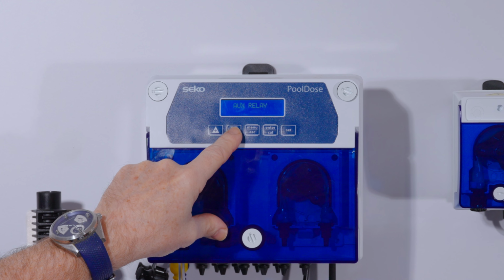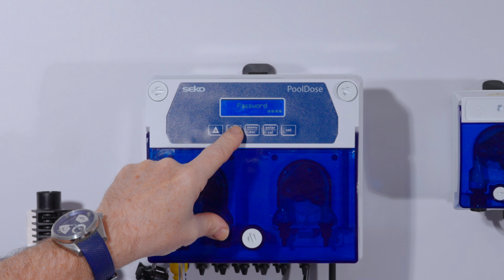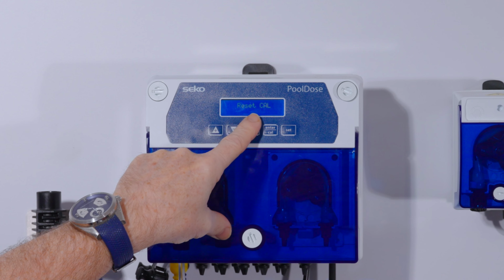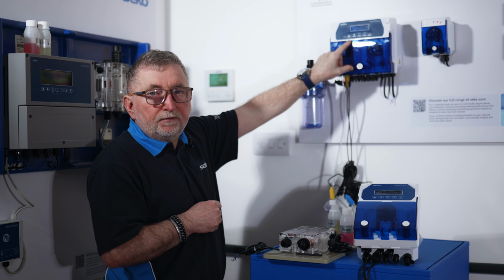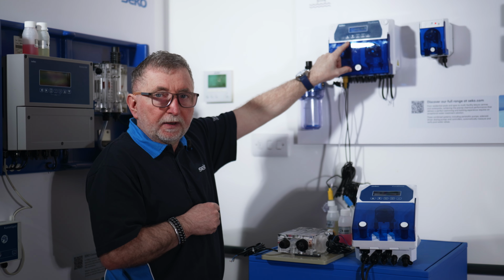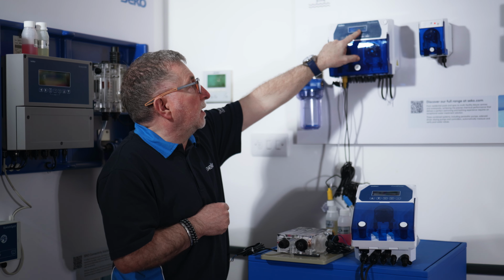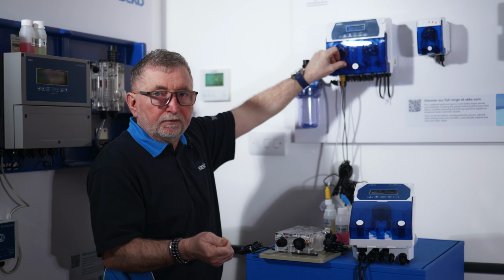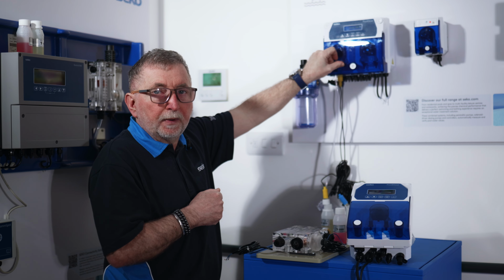We have an auxiliary relay alarm. The system is password protected, and we can also reset the cal. The reason for this is if you use a reference solution instead of the buffer solutions, you should always reset the calibration if you're going to revert to using the buffer solutions. So you basically go back to a default. We can also reset all parameters, and we have a control panel where we can view the electrical inputs for the probes. Wi-Fi information, and the reed normally open is another device we use for detecting flow of water.